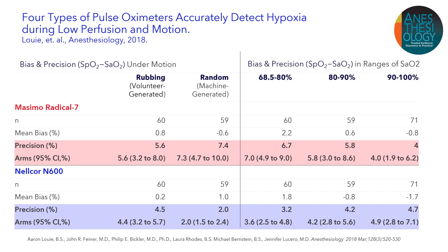And what we can see is that Nellcor, as shown on the bottom, was able to achieve accuracy better or comparable to the competitors in these various different situations, looking at random or volunteer-generated types of motion. Having a better understanding of how Nellcor is engineered, I hope that you can appreciate these results — putting an emphasis on the pulse and the patient, identifying noise and motion noise, being able to scrub that noise out with cardiac gated averaging to achieve excellent performance.